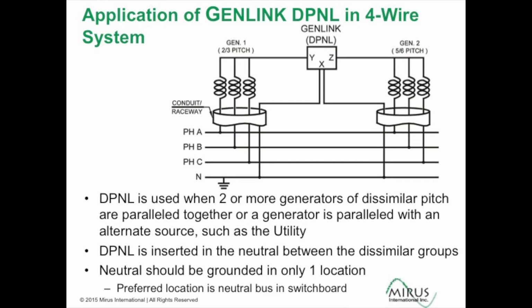Here's an application of the DPNL in a four-wire system. We're showing two generators, one with a 2/3 pitch and the second with a 5/6 pitch. But the exact pitch configurations don't matter in this application. It's just that if they're different, then you're going to get circulating current. So if it's a 4/5 and a 5/6, there'll be circulating currents. So any configuration of dissimilar pitches is going to result in circulating currents.